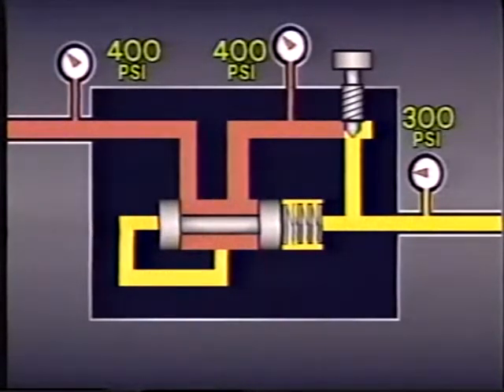When using this kind of pressure compensated flow control valve, the system's relief valve setting must be at least as high as the workload pressure and the spring pressure. Otherwise, the valve will not be able to compensate for changes in pressure.